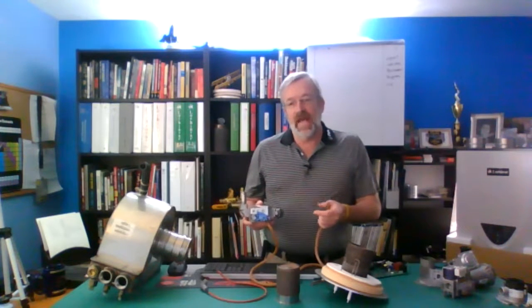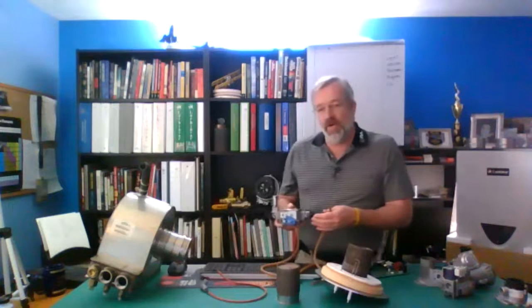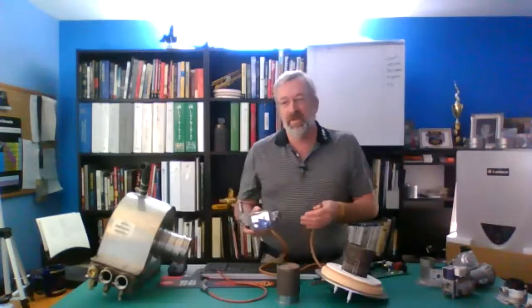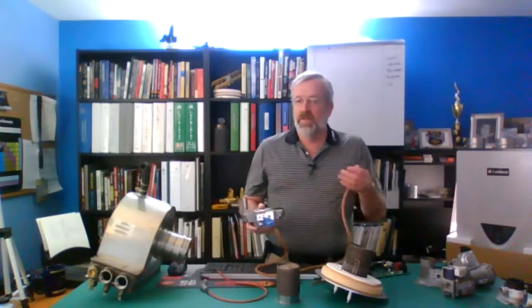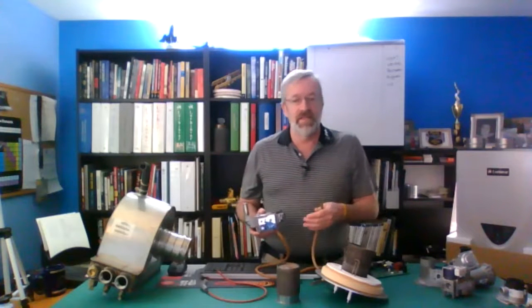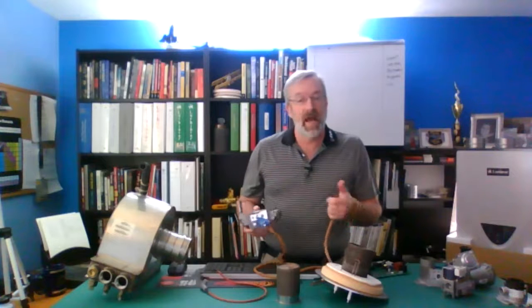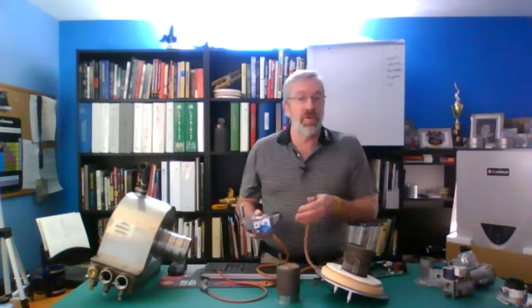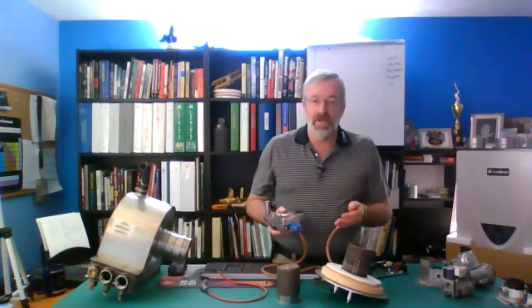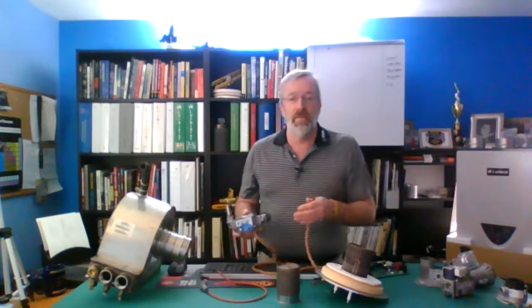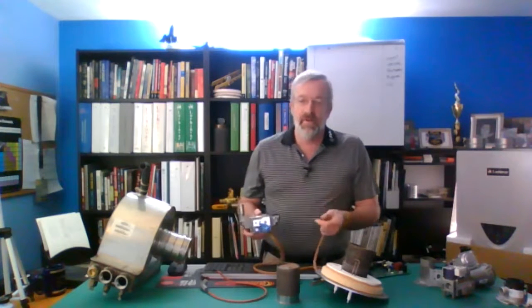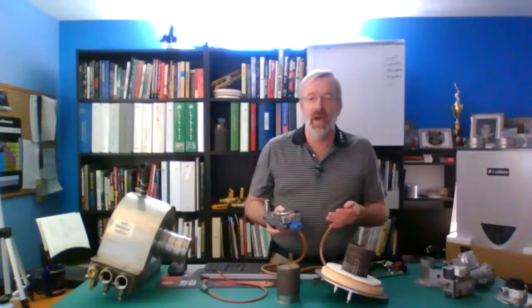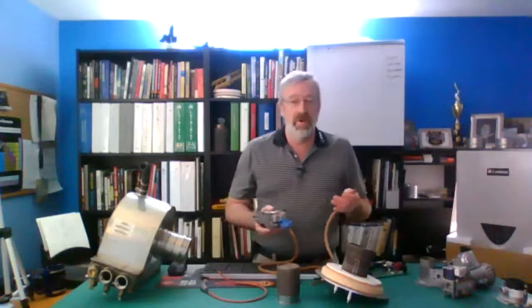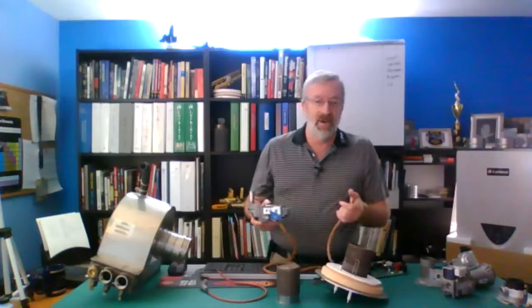Now, if we've got 8 inches of gas, and now we're going to set it into trial for ignition, we want to see that gas valve open. We want to see a drop in gas pressure, maybe an inch, maybe 2 inches. So if my 8 inches were to drop down to 6 inches, that would tell me I had good gas pressure and I have adequate gas volume. Now, if my gas pressure goes from 8 inches to like 2 inches, I have good gas pressure, but I don't have enough volume for the size of my boiler, is really what's happening there. So at that point in time, we want to stop. We want to track that down, see what's going on. Do I have a problem with my meter, with my regulator, my gas pipe sizing, all of those things?